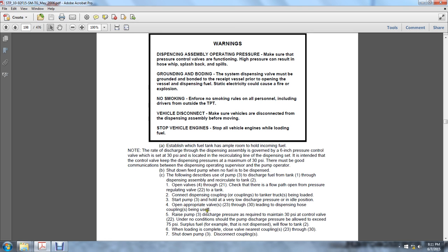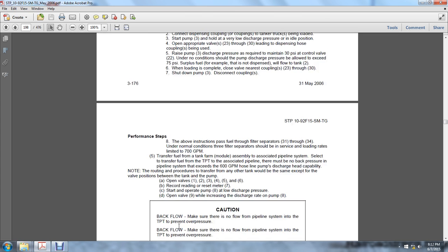Raise pump 3 discharge pressure as required to maintain 30 psi, controlled by the pressure control valve 22. Under no conditions should the pump discharge pressure be allowed to exceed 75 psi. Surplus fuel, for example when there is no dispensing, will flow to the tank. When loading is complete, close the valve nearest coupling 23 through 30, shut down the pump, and disconnect the coupling.